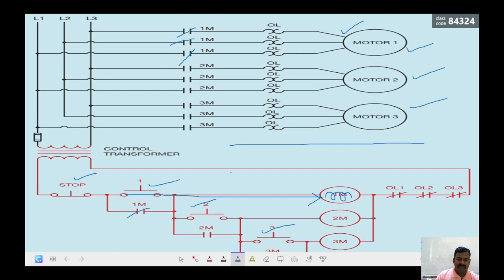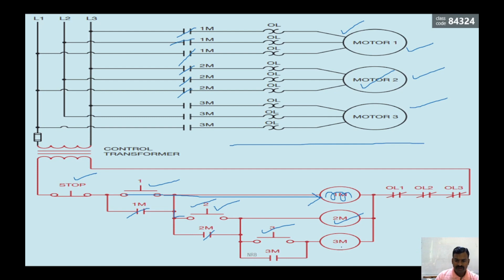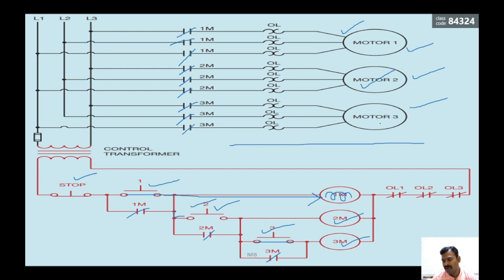When those three contacts close, motor one runs, and it also provides the electrical path for the second motor. When the second switch is pressed, the second coil gets energized, its contacts close, and motor number two runs. Once that is done, the third contactor coil is ready for signal from the third switch. When that switch is operated, the energy is received in the coil, the coil energizes, the contacts close, and motor number three runs.